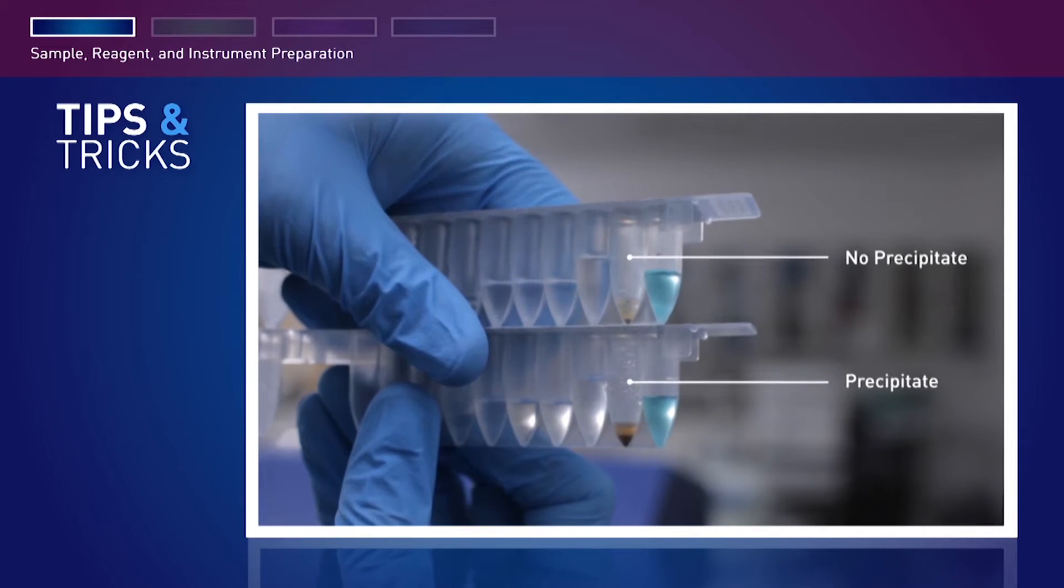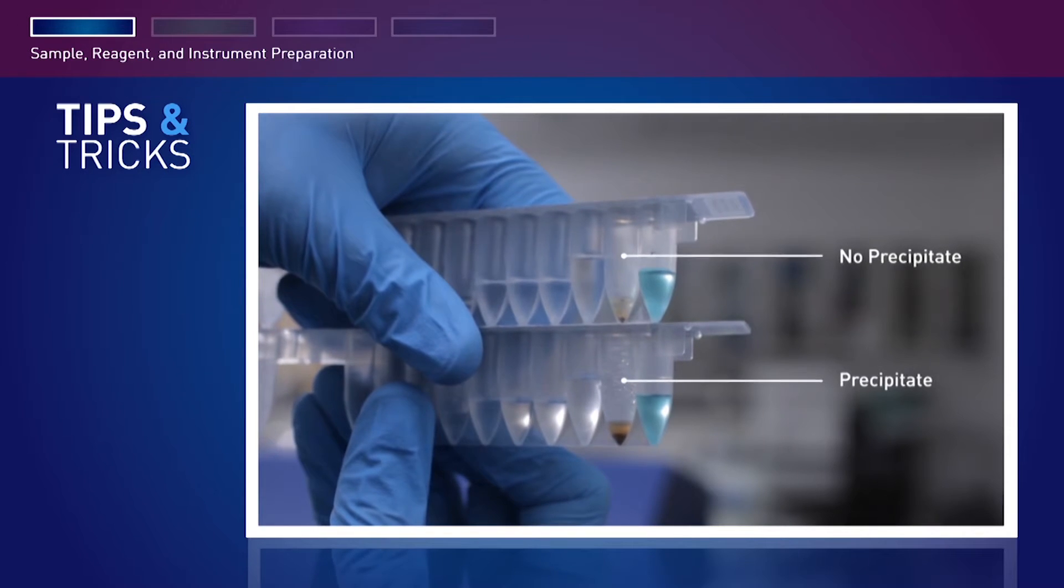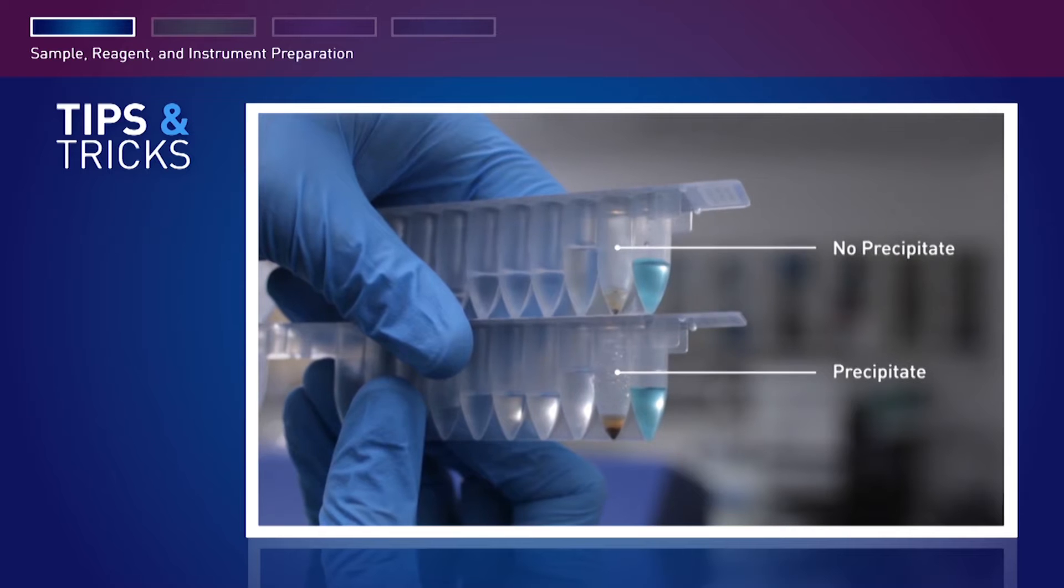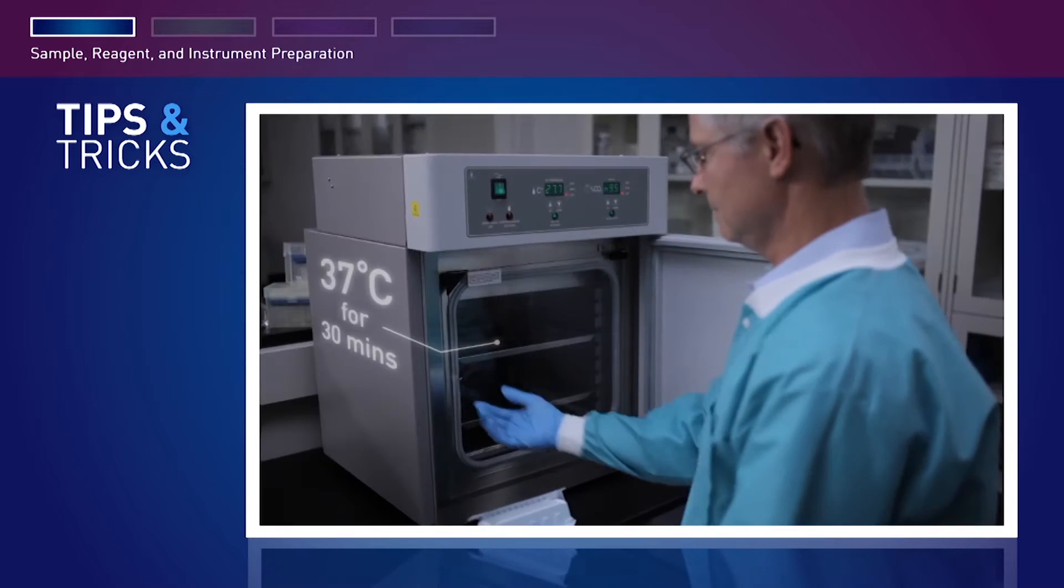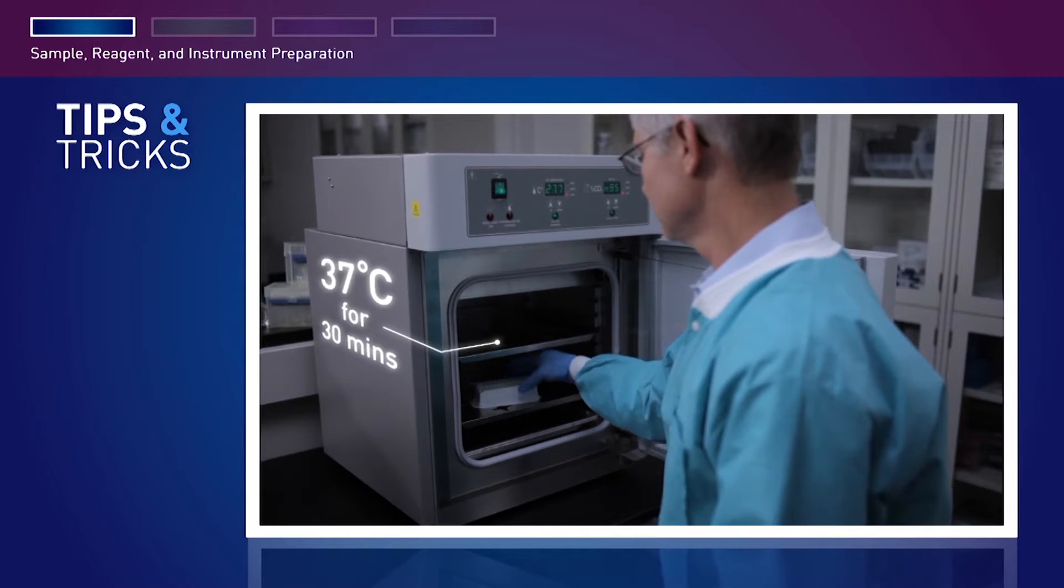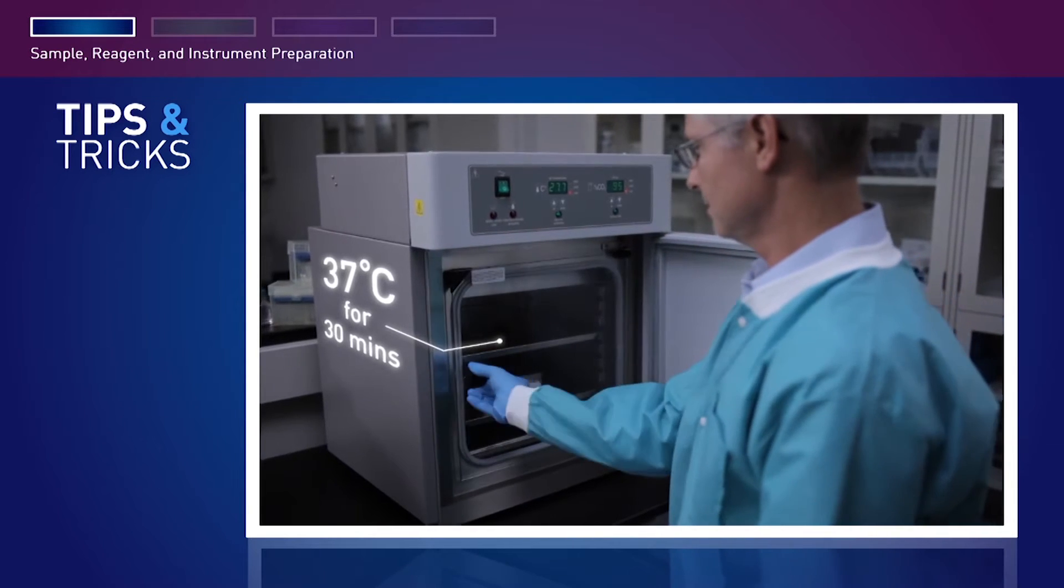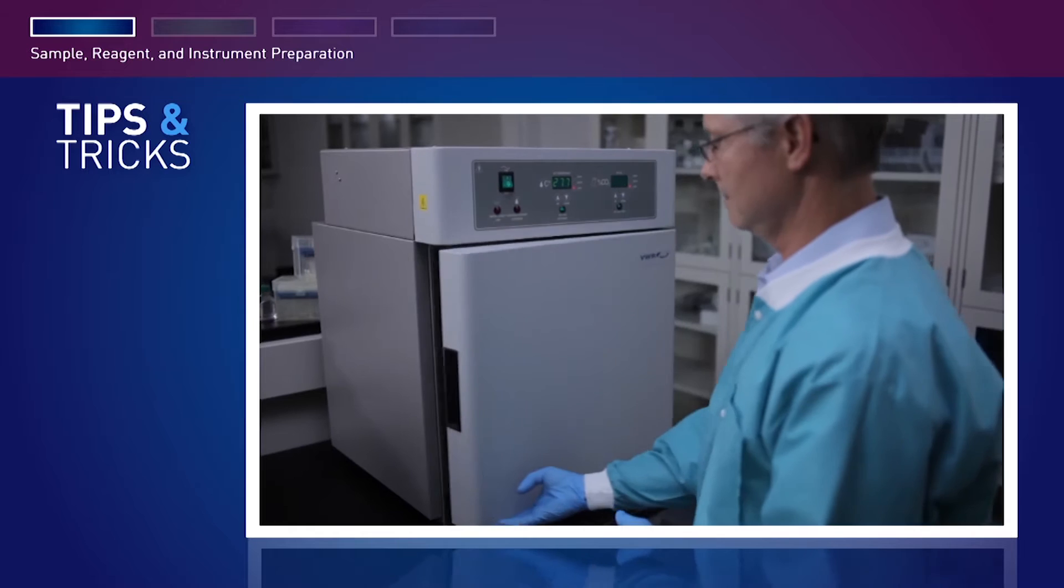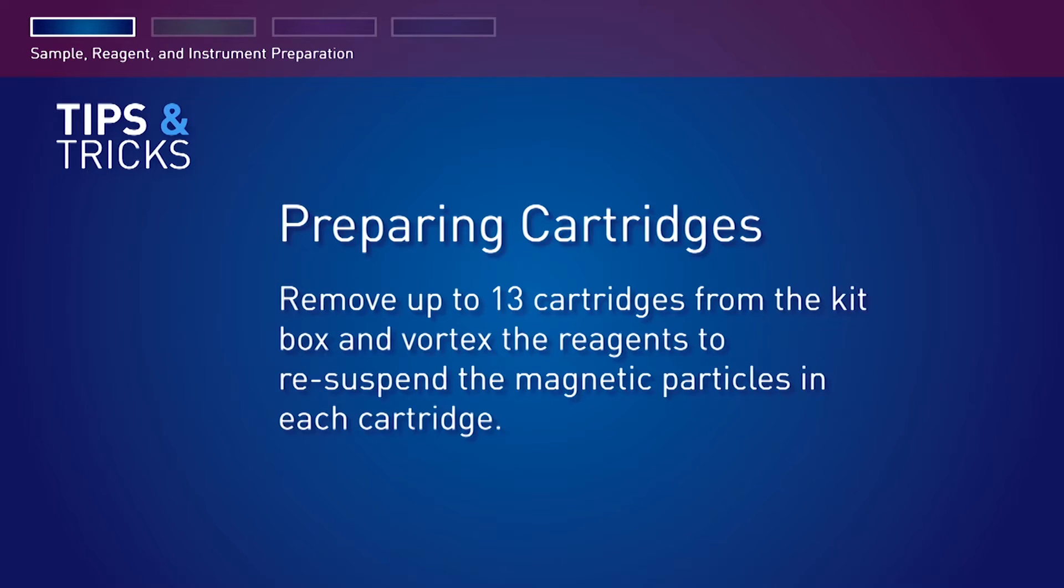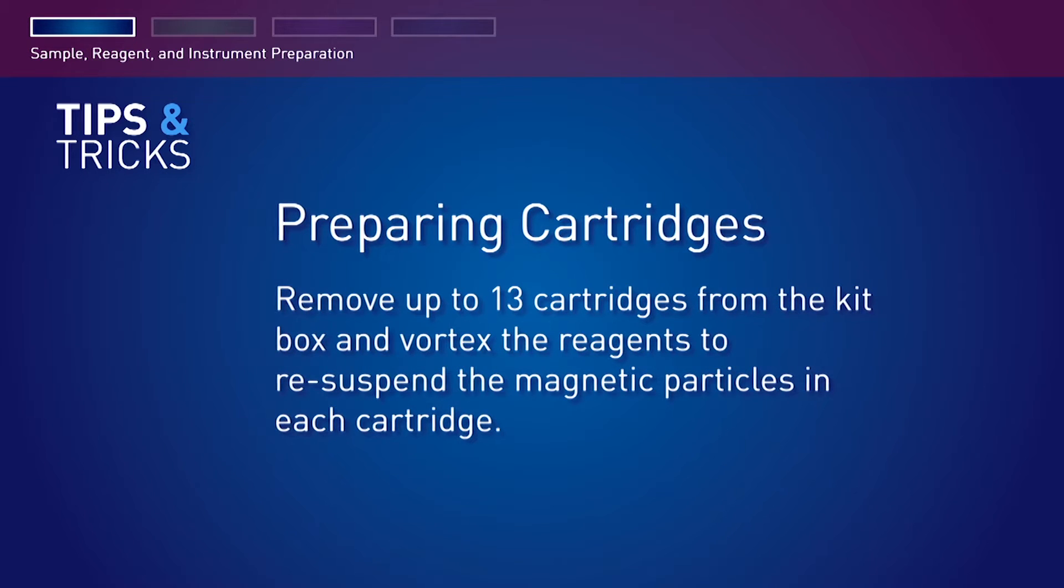If precipitate forms in compartments 1 or 2, lysis buffer and magnetic particle suspension, heat the cartridge in an incubator at 37 degrees for 30 minutes or until the precipitate is no longer visible. Heat only those cartridges that you plan to use that day.